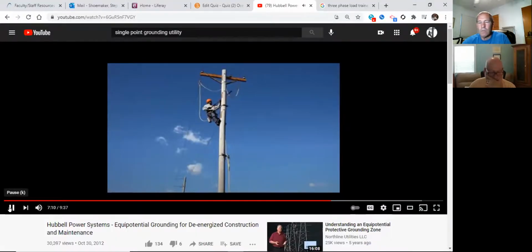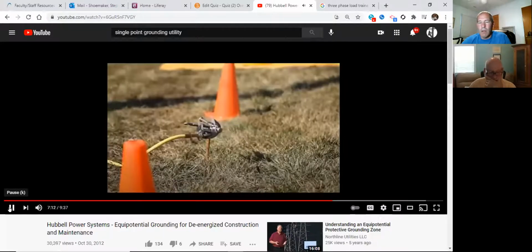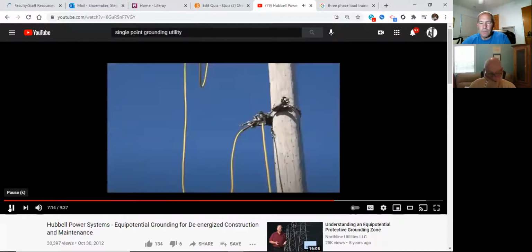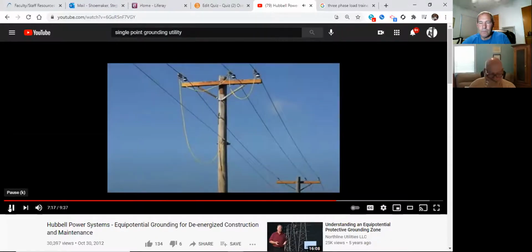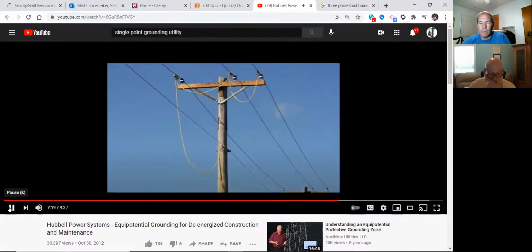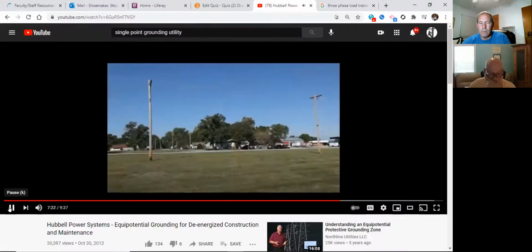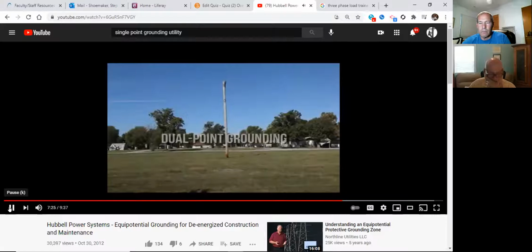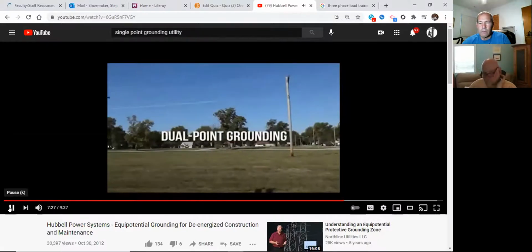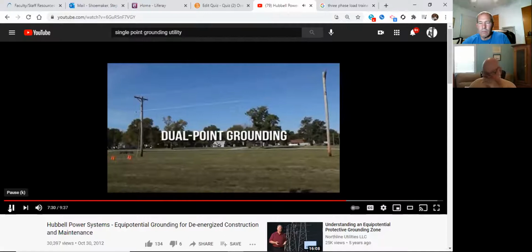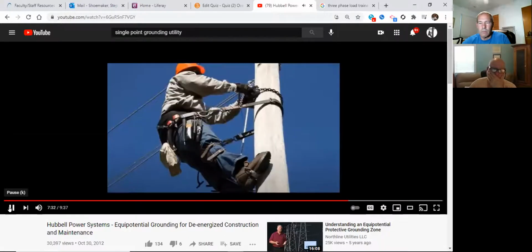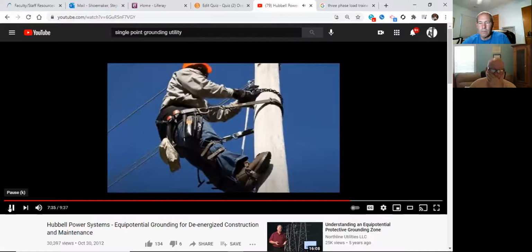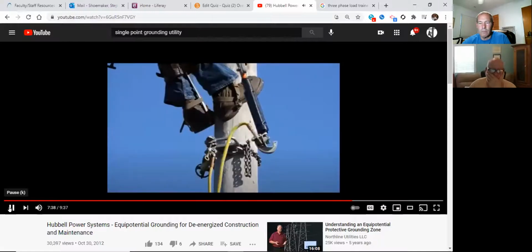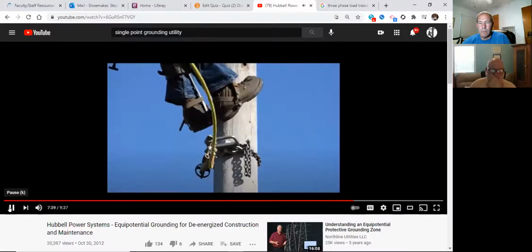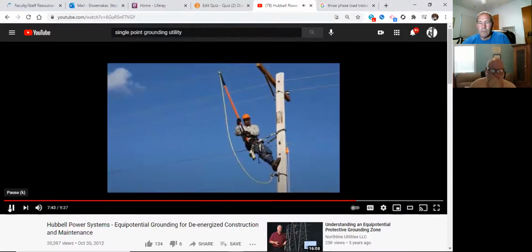Procedure in the same order here. Again, it's from ground rod to cluster bar to neutral to the 3 phases. This establishes what's known as dual point grounding. For the worksite, the pole in the middle. Grounding at the worksite begins with a cluster bar. The temporary ground he's installing here at the center pole, the actual worksite, is known as a personal ground.